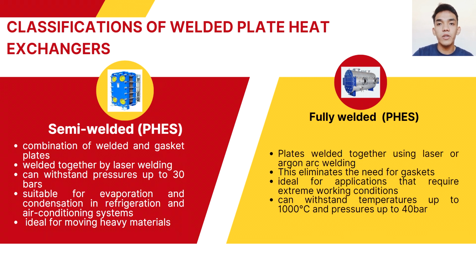These are combination of welded and gasket plates, making them an ideal choice for applications that require the handling of relatively corrosive media. So, these heat exchangers are configured by assembling two heat transfer plates that are welded together by laser welding. The only gaskets in contact with the medium are the two circular porthole gaskets between the welded plate pairs, which are available in highly resistant elastomer and non-elastomer materials. So, this design allows the semi-welded PHEs to withstand pressures up to 30 bars. This makes them suitable for evaporation and condensation in refrigeration and air conditioning systems, as well as for ammonia fluid. Additionally, the relatively low chance of fluid loss makes semi-welded plate heat exchangers ideal for moving heavy materials.